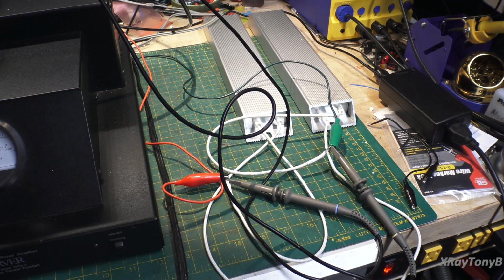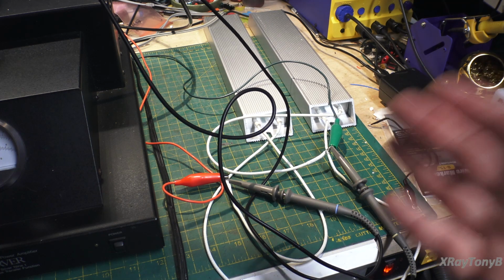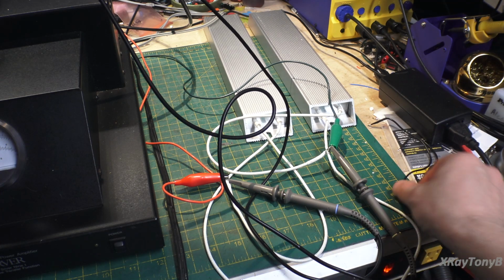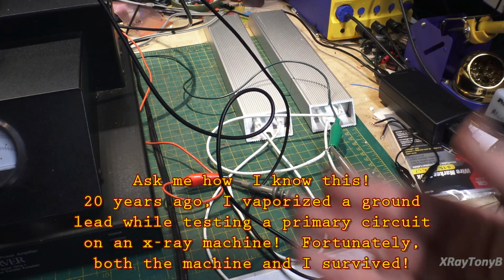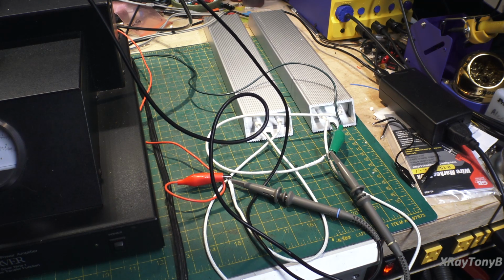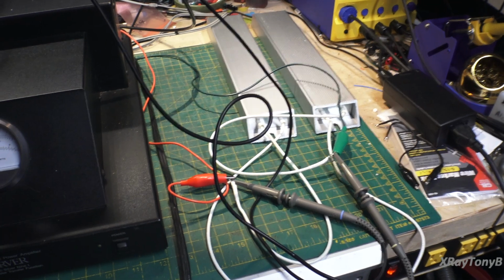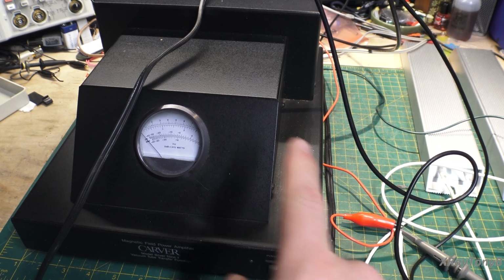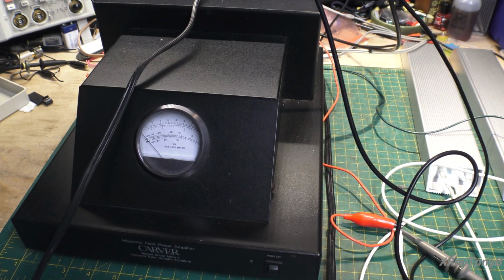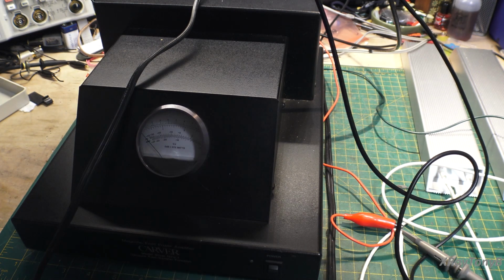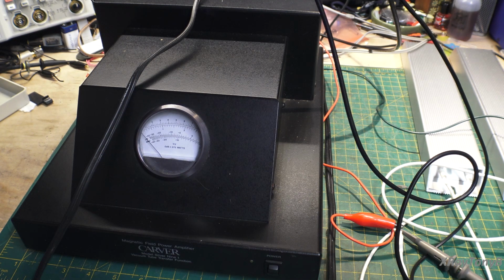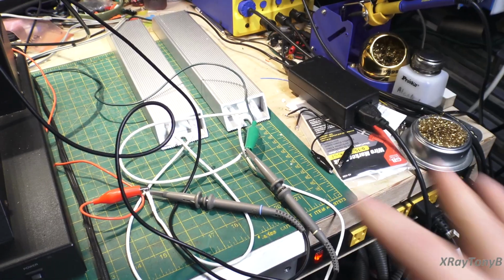So anything that is connected to your AC outlet and is unisolated, you pose a risk of a severe short. At the very least, you will blow this wire apart. At the very most, you could cause a fire, you could damage the equipment, you could get shocked or electrocuted. Very dangerous. This isolates that. Now, I would still put the scope on an isolation transformer if we were going to do that. There are some tests where you will actually be putting your scope at mains voltage potential on the mains. The instructions tell you to use an isolation transformer for the scope. It's still not my favorite way of doing things because even though it's isolated electrically on that transformer, you're still putting one leg of your AC on that outside ground terminal, which I still don't like. So even in addition to the isolation transformer, your best bet is to use this differential mode.